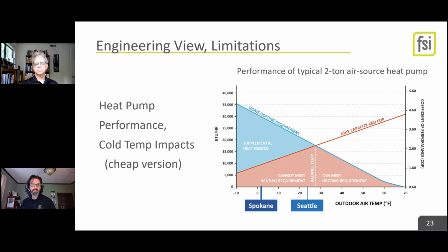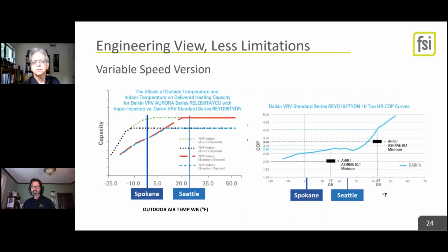So a regular heat pump would have this thing where your heating requirement, supplemental heat, that thing over there in blue, you can see I put the design temps for Seattle and Spokane. Those are the 99.6 percentile. And so Seattle, you're probably going to need electric resistance. In Spokane, you're definitely going to need it. And these are for the cheap version, single speed compressors. Let's go to the next slide.